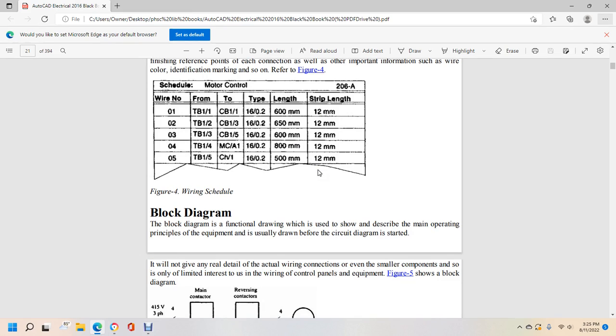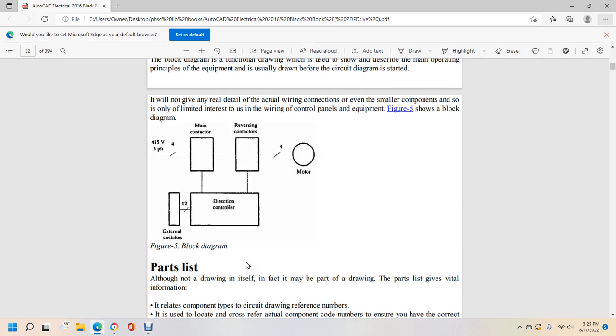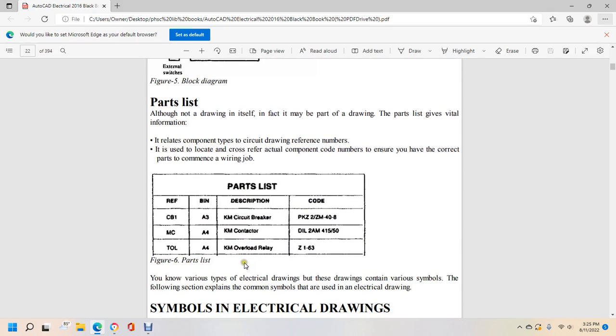Block diagram and functional diagram. These show a description of the main operating principles of the equipment, usually drawn as a diagram. It will not give any real detail of the actual wiring connections, not even the smaller components, only limited to the wiring, control panels, and equipment shown in the block diagram. Here it shows the panel in the block diagram with the main contactor and reversing contactors of the motor with direct control external switches. Now, the part list.